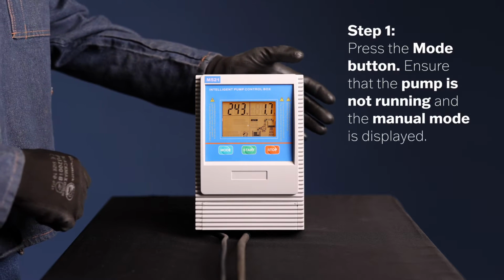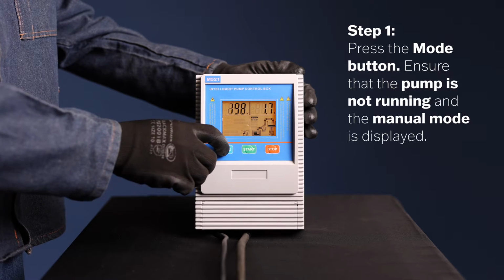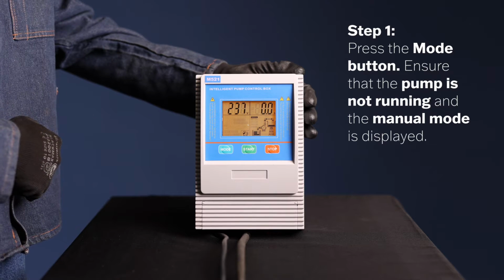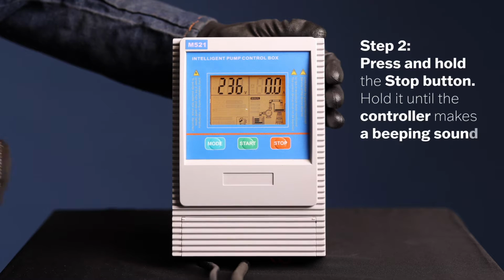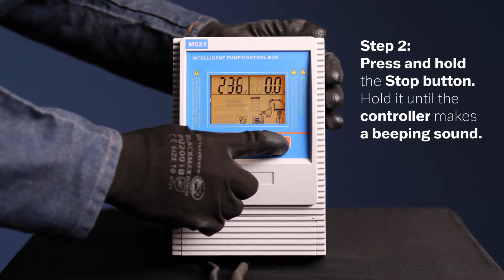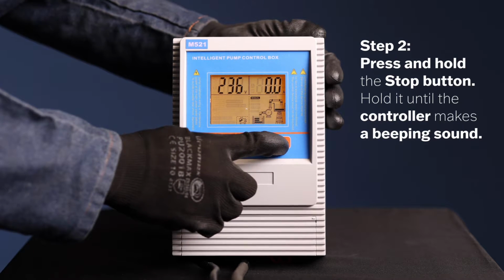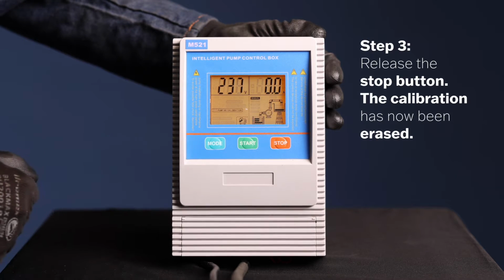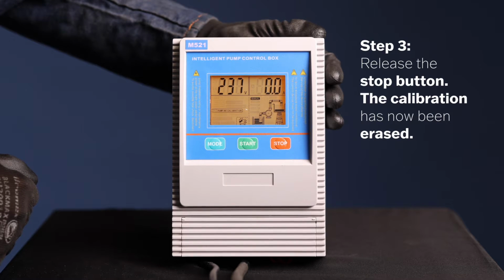Step 1. Press the mode button located on the controller. Ensure the pump is not running and the manual mode is displayed on the screen. Step 2. Press and hold the stop button located on the controller. Hold it until you hear a beeping sound from the controller. Step 3. Release the stop button. By doing so, you have successfully erased the calibration on your M521 controller.